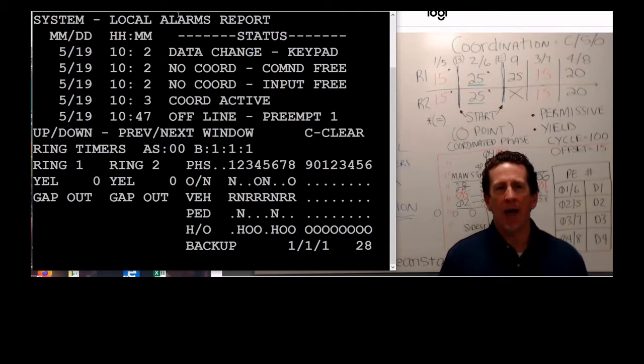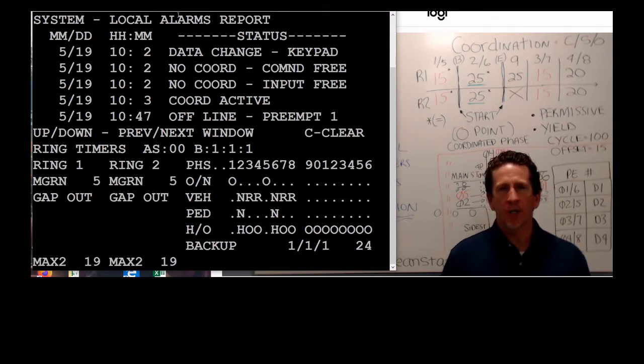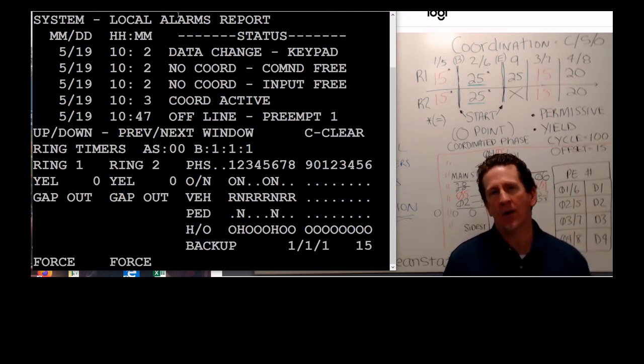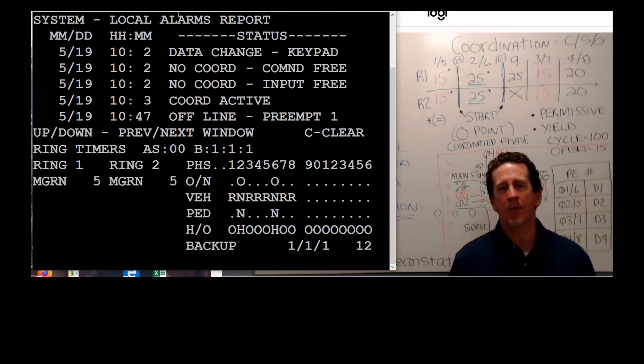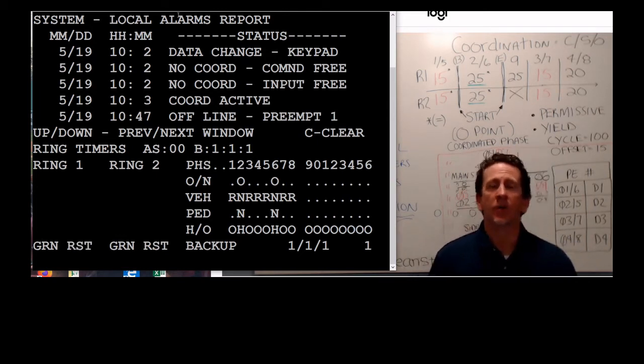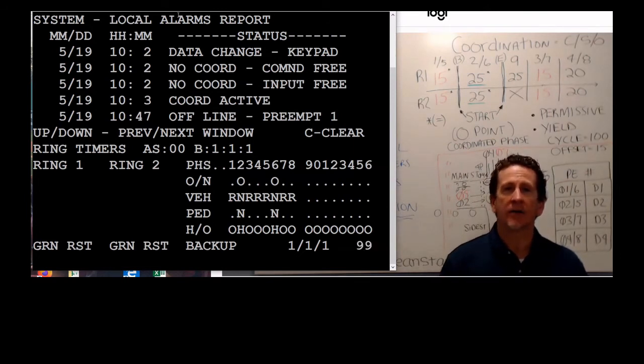So when our BIUs go bad, and there are 3 of them, it'll give me a frame fault code number. And that code number in the back of a Siemens manual will tell you, for example, 147 is BIU 1, 148 is in the rack, 129 is the MMU. So it helps you identify which device is giving you the problem, or it could also be the harness that is the problem, the SDLC harness, because there's a breakdown in the ability to communicate that information.